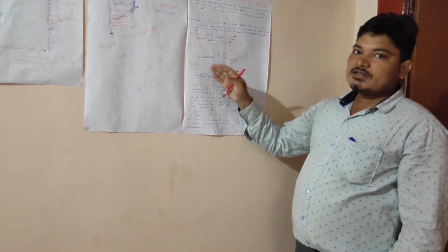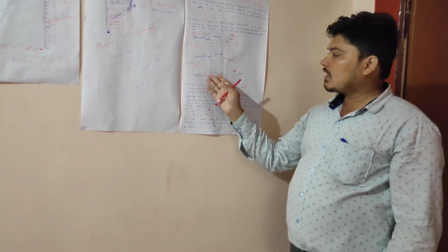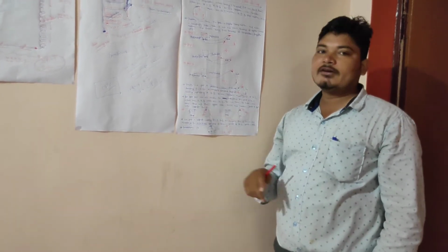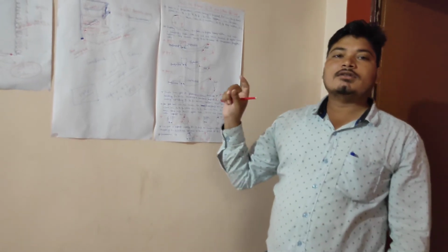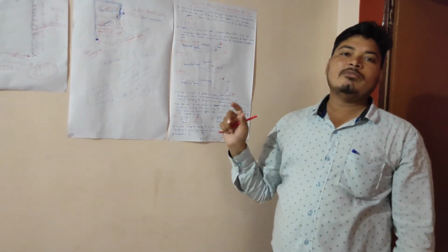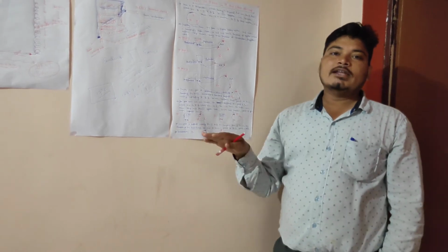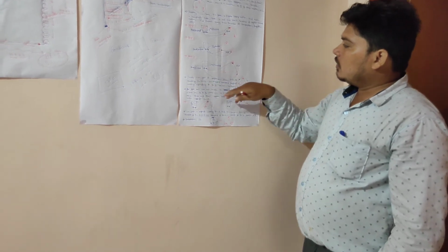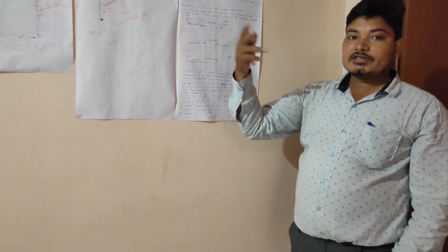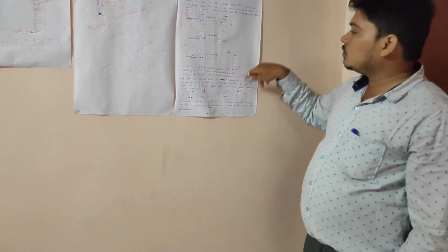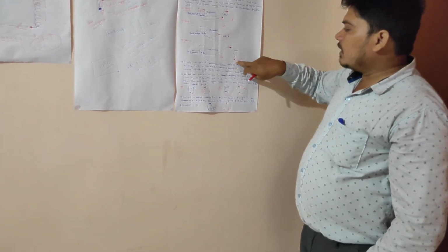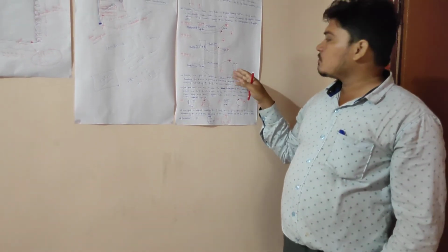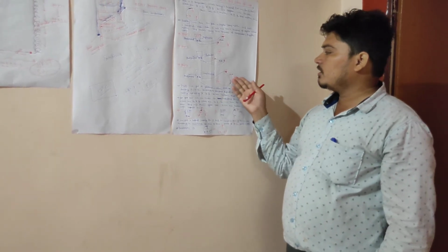Step 3. Next step will be the same. Take a digital clamp meter which has two electrical wires, one red wire and another black wire. The same digital clamp meter, and the mode will be the same, continuity mode. There are no changes in the digital clamp meter. In step 3, take a reading on the rest two electrical terminals of the compressor. Between A and C we get 17 ohm. This is the resistance value between A and C.